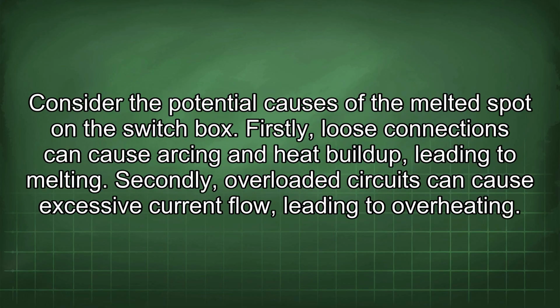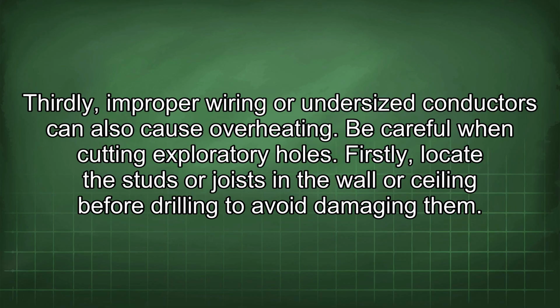Consider the potential causes of the melted spot on the switch box. Firstly, loose connections can cause arcing and heat buildup, leading to melting. Secondly, overloaded circuits can cause excessive current flow, leading to overheating. Thirdly, improper wiring or undersized conductors can also cause overheating.